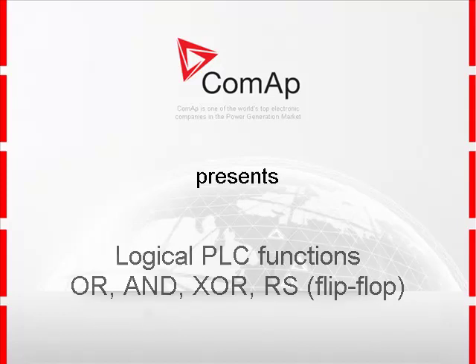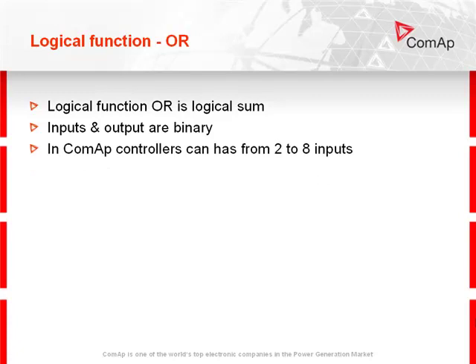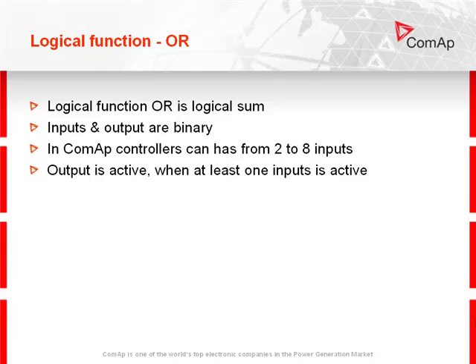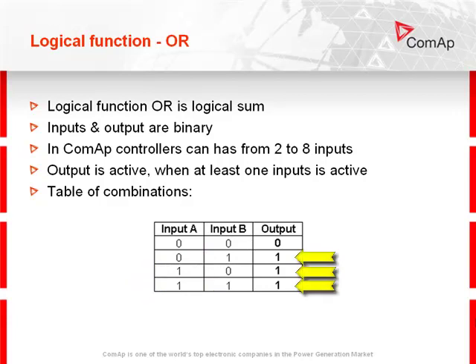COMAP presents logical PLC functions OR and XOR. Logical function OR is a logical sum. Inputs and output are binary. In COMAP controllers it can have from 2 to 8 inputs. Output is active when at least one input is active. In the table of combinations you can see that at least one active input causes an active output.